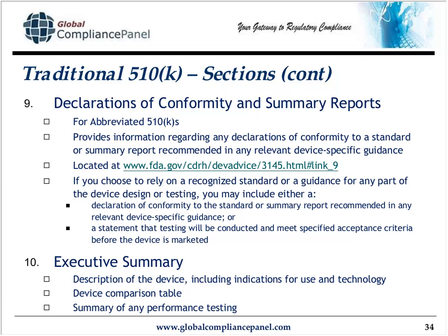Section 10 is the executive summary. It's a description of the device, indications for use, a couple of words on the technological aspects of it, a device comparison table between your device and the predicate device. We've already gone over previously the ways to identify substantial equivalence and a summary of the performance testing that was done.